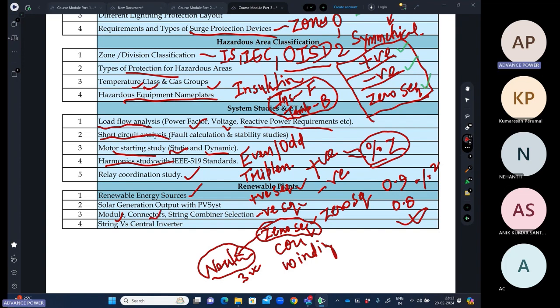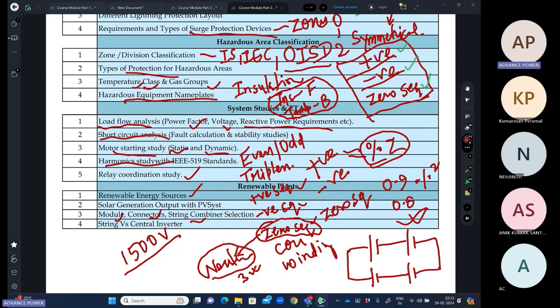We have different connectors, MC4 connectors, string combiner box selection. So how the series parallel connections are being done to maintain the voltage rating, standard voltage rating of the module and the inverters. Then we'll see the connection between module to module we do. So it's like a battery. We join in series and we join in parallel connections. So what are the advantages and disadvantages we are facing in series and parallel combinations? Like, voltage is getting added up in series and current is getting added up in parallel. So all those things we'll study there, and how we'll reach the 1500 volt and the ampacity.